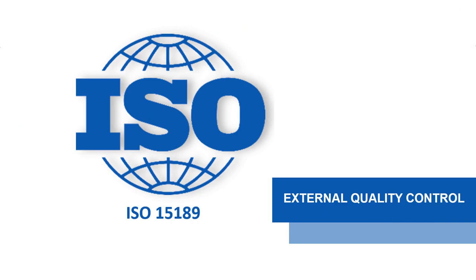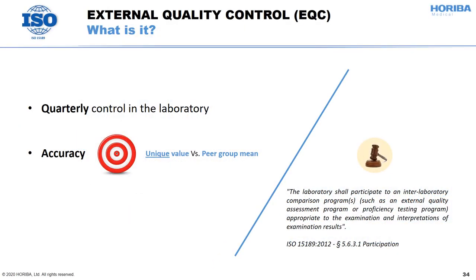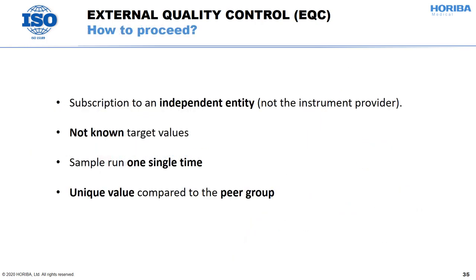The last quality control is the external quality control, or EQC. It is generally done quarterly and allows to specifically assess the accuracy. The EQC is also a requirement for the ISO 15189 standard. The laboratory will receive a control sample from an entity independent from the instrument provider, without delivering any target value. So the laboratory will run a blind test and only know the target value after having sent its results. It will send only one unique value to be compared to the peer group.